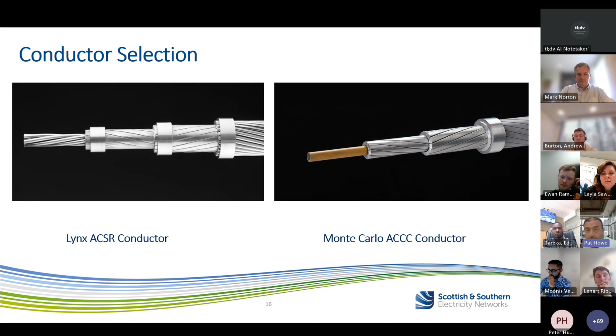What we did was look at all the high temperature, low sag conductors and went through a testing process. This shows the requirements we had. We looked at a traditional conductor, ACSR, but as you can see it didn't meet the capacity requirements we wanted, and it also wasn't fixing our clearance issues.